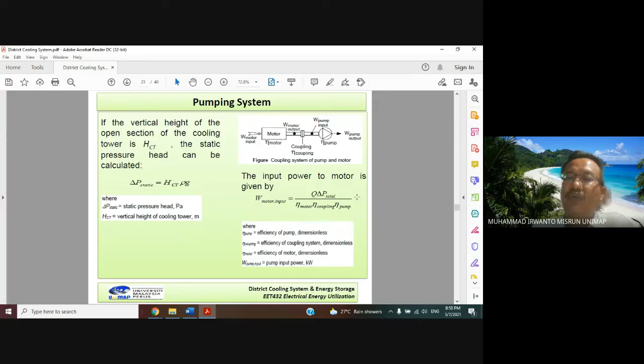And delta P total here is the total friction losses, starting from the friction losses of the pipe and the friction losses of the fittings. There are many fittings: elbows, T-junctions, valves, strainers. Then, if we consider the condenser water pump, the water goes up to the cooling tower, so we also add delta P static, and the friction of the condenser or heat exchanger.